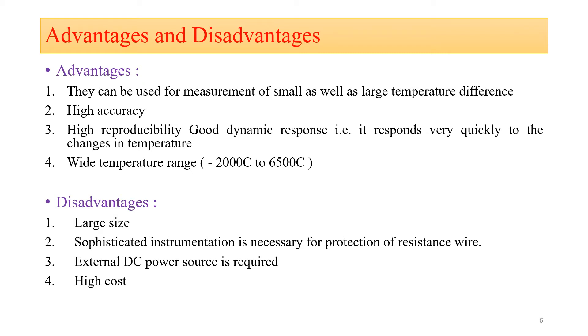The advantages of RTD are: it can be used for measurement of small as well as large temperature differences; they are highly accurate; high reproducibility; good dynamic response — it responds very quickly to temperature changes; and a wide temperature range of approximately -200°C to 650°C. Disadvantages include: large size; sophisticated instrumentation is necessary for protection of the resistance wire; it requires an external DC power supply; and high cost.